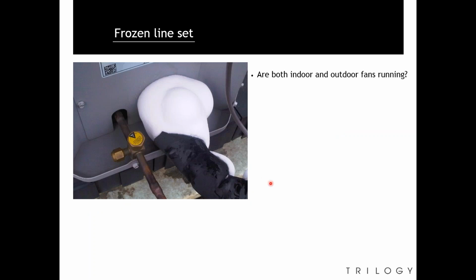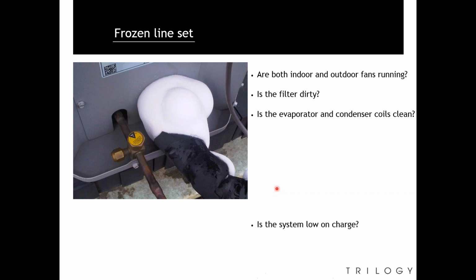Frozen line set. So if we have a frozen line set, immediately pull the disconnect. We want to shut the unit off. Now, are both indoor and outdoor fans running? Is the filter dirty? Are the evaporator and condenser coils clean? Is the system low on charge?